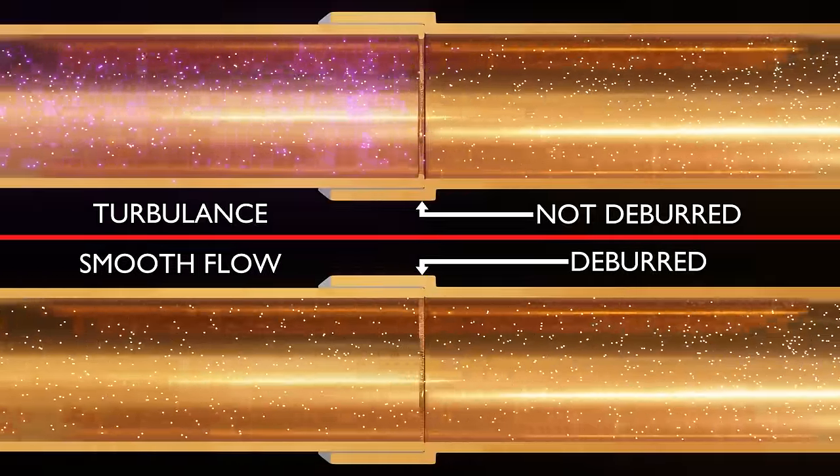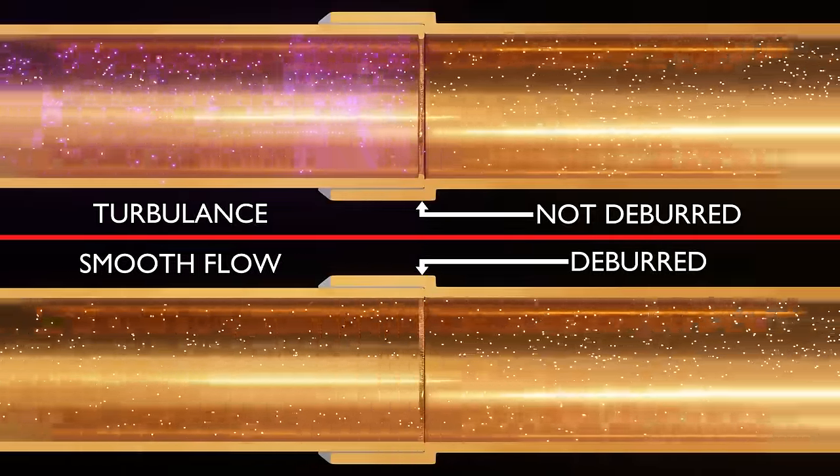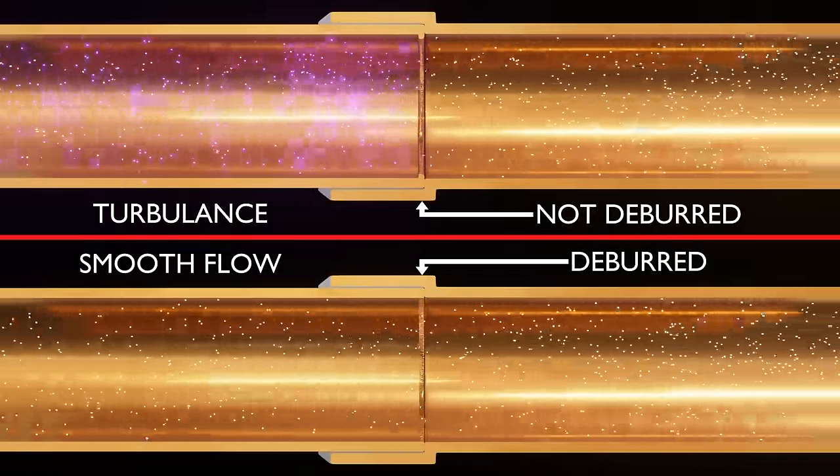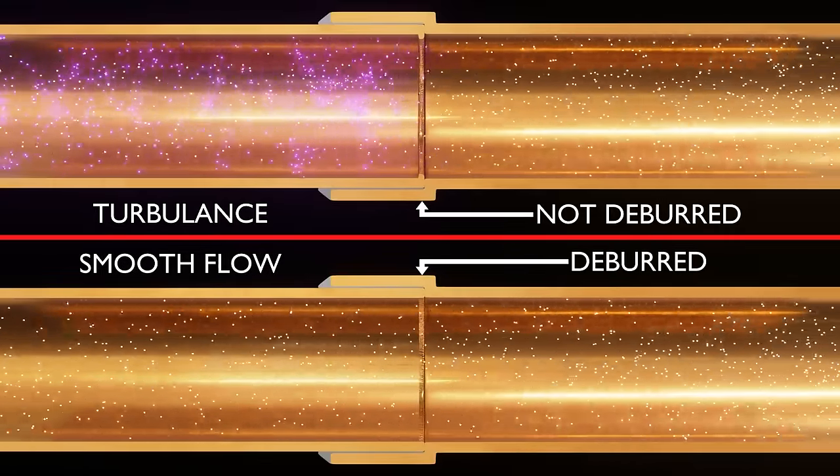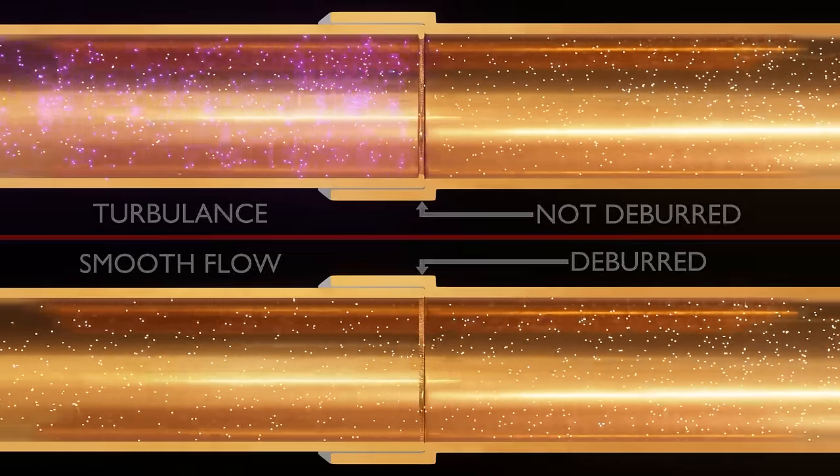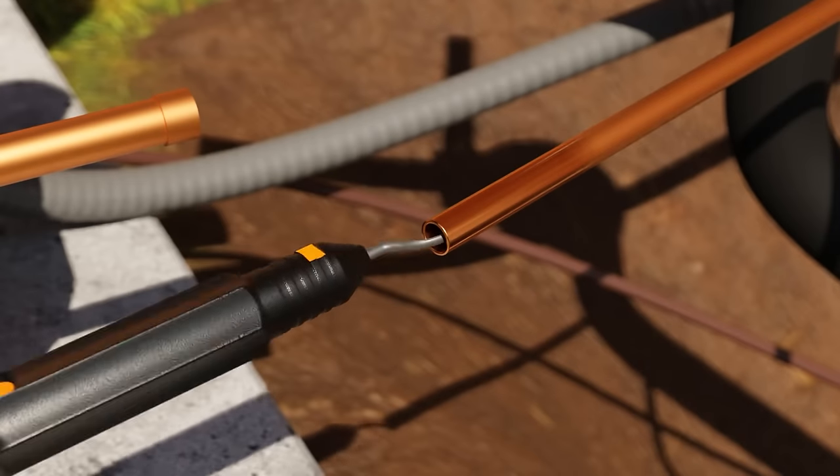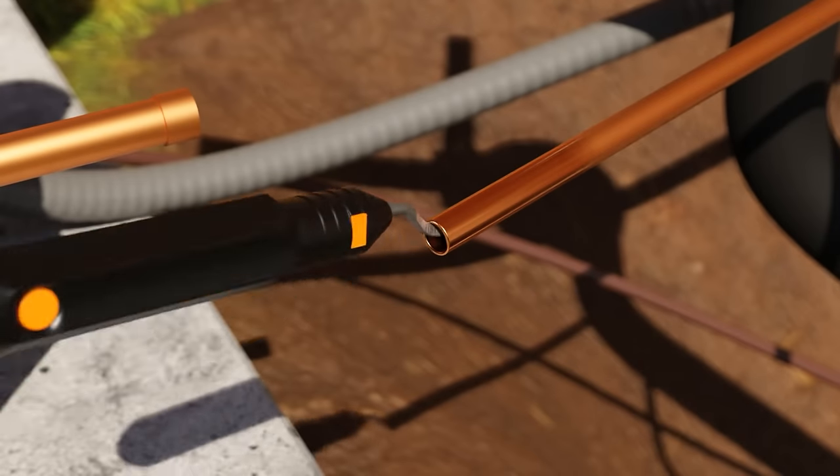Here we show the effects of failing to ream or deburr. It creates turbulence and turbulent flow on the outlet side, resulting in unnecessary friction and resistance to refrigerant flow. Keep in mind that deburring is especially important when making connections like flare connections, where the burr can impact the quality of the flared surface.